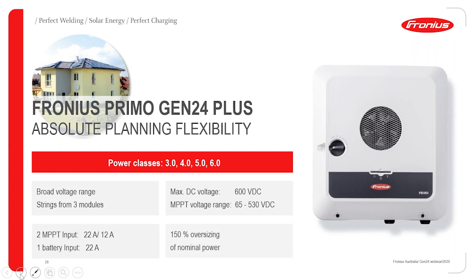The first thing is the inverter has quite a broad voltage range. Compared to a normal Primo with a starting voltage of 80 volts, this one goes lower. It goes to 65, and the MPPT voltage range is 65 to 530 volts. Having this wide voltage range means your inverter can start early, and the minimum number of modules, depending on which modules you use, is 3 to start the inverter. That's quite impressive. The maximum DC voltage would be 600 volts. Here in Australia, we don't go above this number.